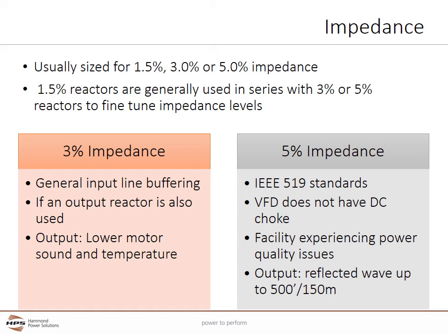Line reactors are usually sized for 1.5%, 3%, or 5% impedance in North America. Other values may be more typical in other parts of the world. 1.5% reactors are generally used in series with 3% or 5% reactors to fine-tune impedance levels and are rarely used separately. Select 3% impedance for general input line buffering. If an output reactor is also used, a 3% line reactor should be considered due to the total voltage drop of two line reactors. 3% line reactors can be used on the VFD output to lower motor sound and temperature rise.